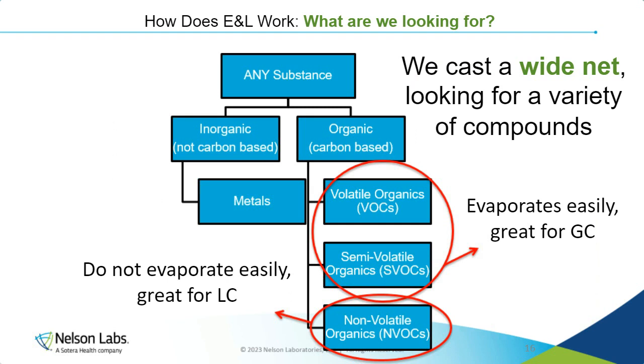When we perform this extractable and leachable study, we are essentially casting a very big net, looking for a large variety of compounds within the extract. The substances we could be identifying are either inorganic or organic based. Our ICP-MS or ICP-OES will pick up any metals, while our GC-MS will pick up any volatile organics or semi-volatile organics. And then lastly, we can identify any non-volatile organic compounds with LC-MS.